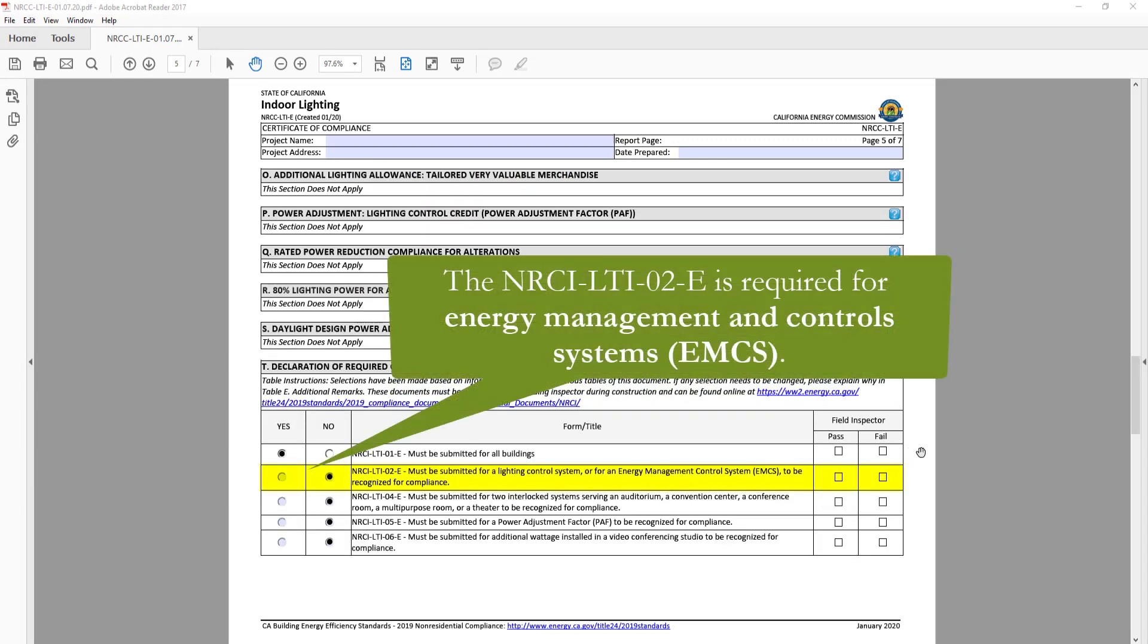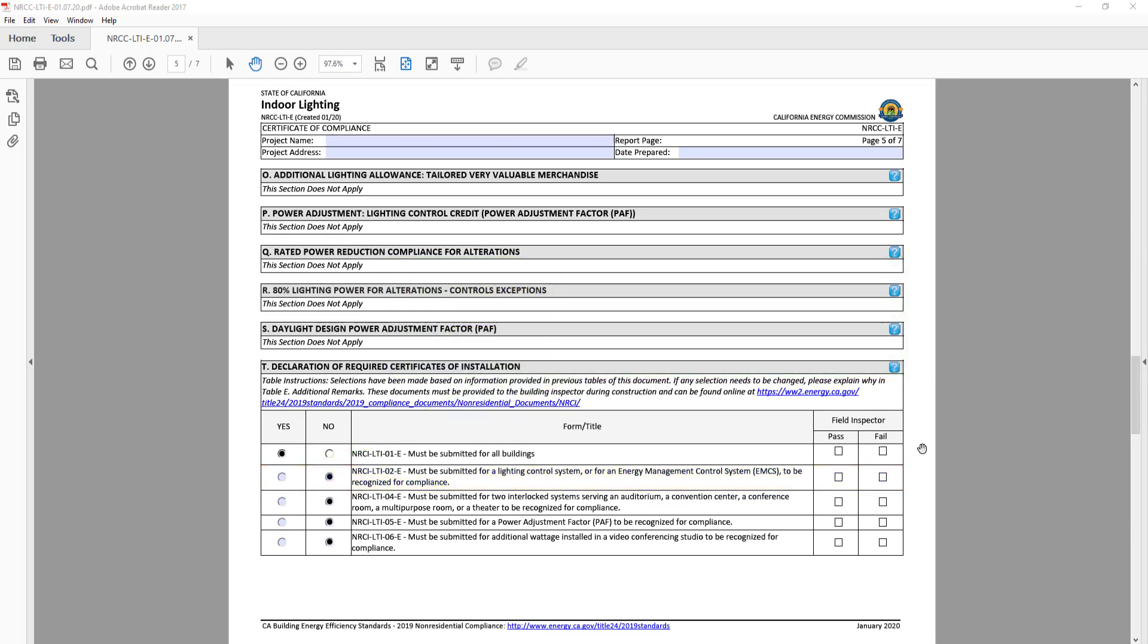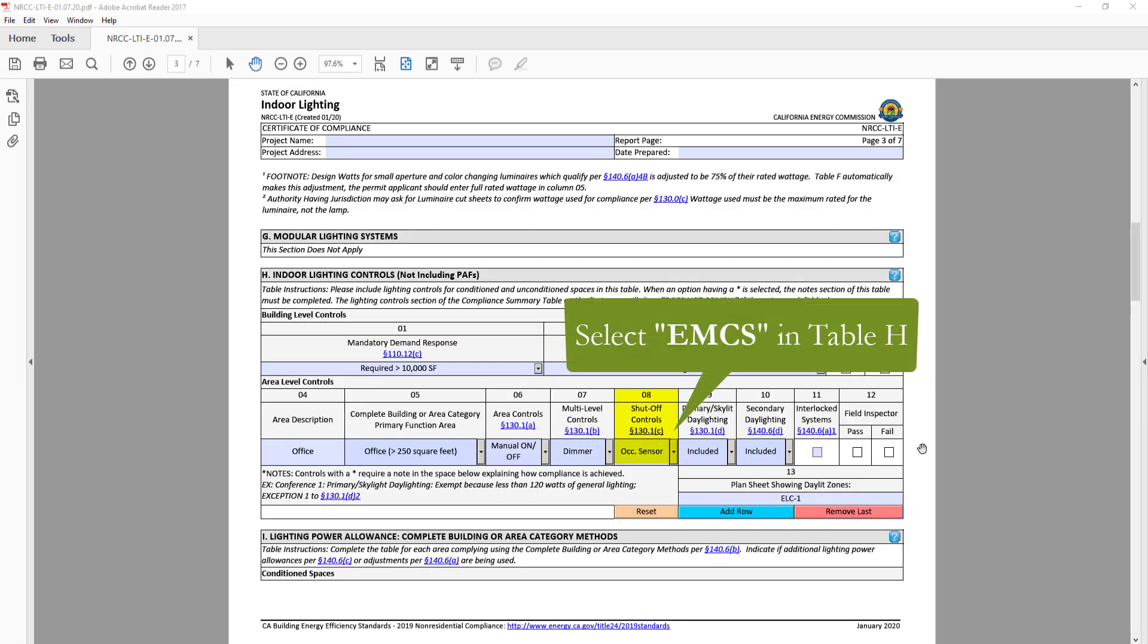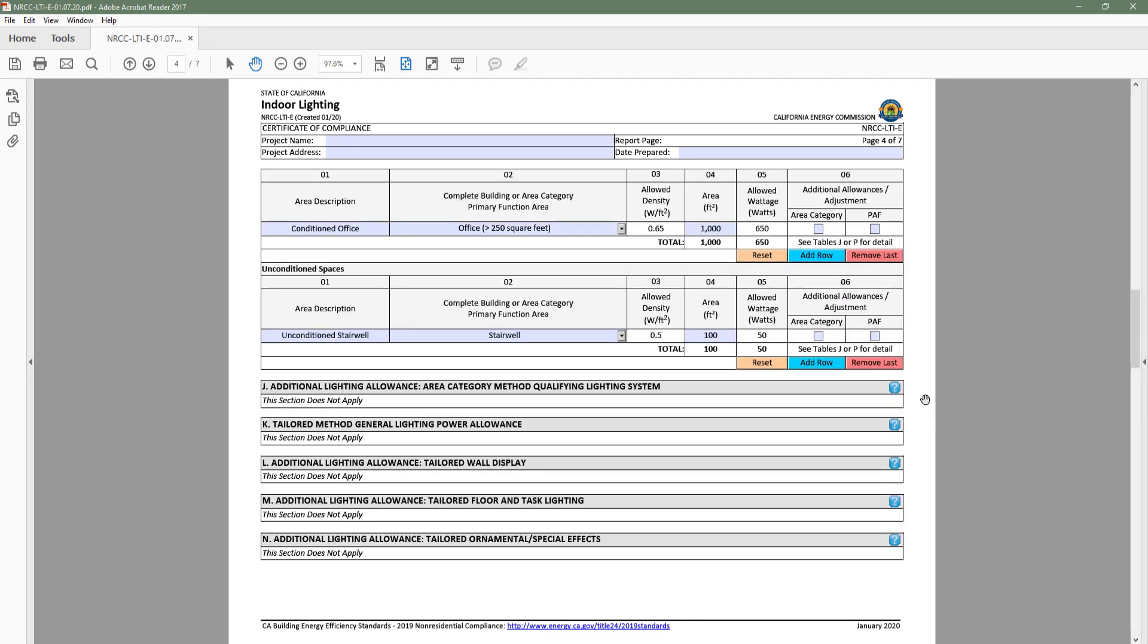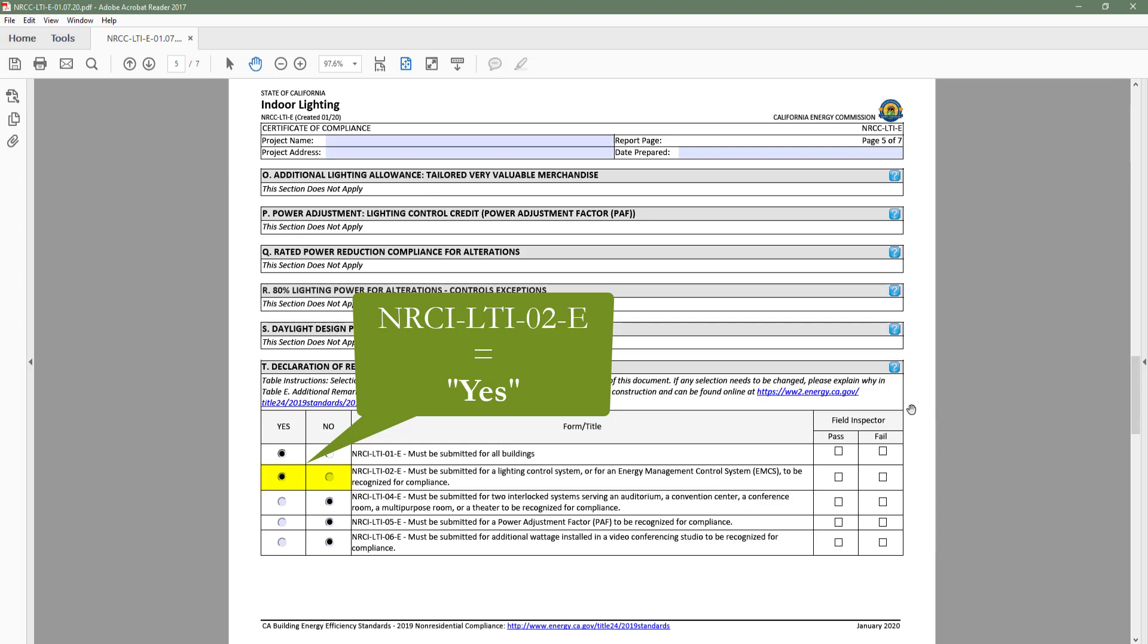For example, the NRCI-LTI-02-E is required when energy management and control systems have been installed. So if we select EMCS in table H lighting controls, the NRCI-LTI-02-E moves to yes.